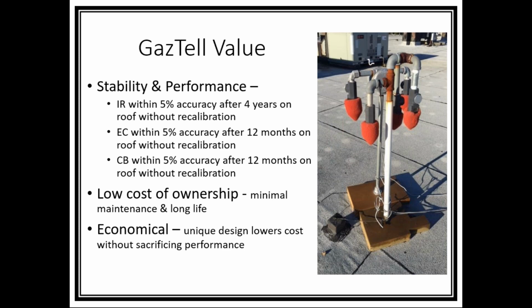Having said that, the infrared GazTell has stayed within a 5% accuracy. We quote 5% accuracy. It stayed within the 5% accuracy for 4 years up on the roof. The electrochem stayed within the 5%, and it's been up there for 12 months without a recalibration. The catalytic bead, the same thing. It stayed within its 5% accuracy. It's been up on the roof for more than 12 months without a recalibration.